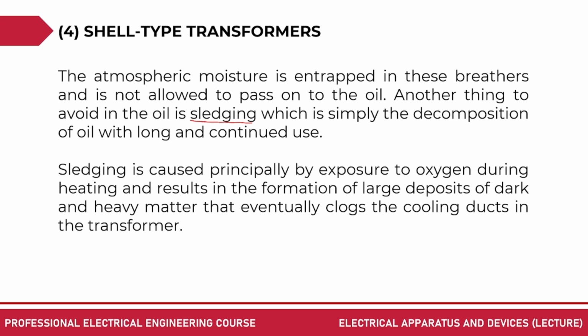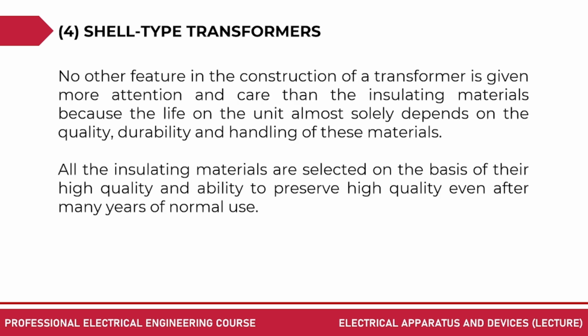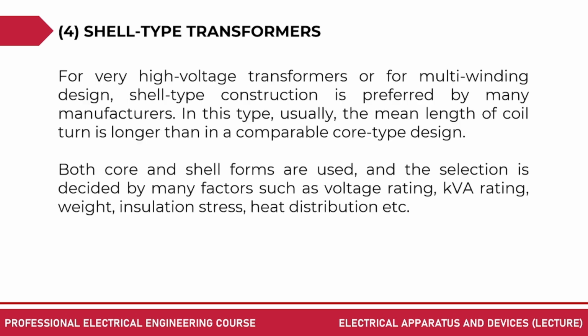Sludging is caused principally by exposure to oxygen during heating and results in the formation of large deposits of dark and heavy matter that eventually clogs the cooling ducts in the transformer. That's why there are researches or theses about the replacement of the oil, or which material to be used, and a lot more of this. No other feature in the construction of the transformer is given more attention and care than the insulating materials because the life of the unit almost solely depends on the quality, durability, and handling of these materials. All the insulating materials are selected on the basis of their high quality and ability to preserve high quality even after many years of normal use.